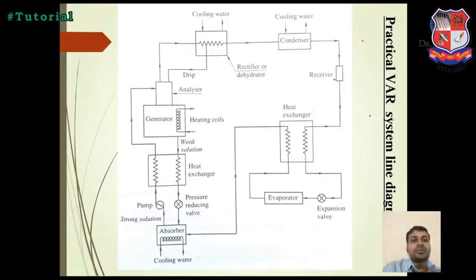Mixing of H2O vapor and NH3 vapor creates a strong solution, but the H2O and NH3 coming from the evaporator are in vapor form. We have to cool it with an external source, which converts it from gas form to liquid form. Then this liquid strong solution is pumped by the pump and returned to the generator for running the cycle.